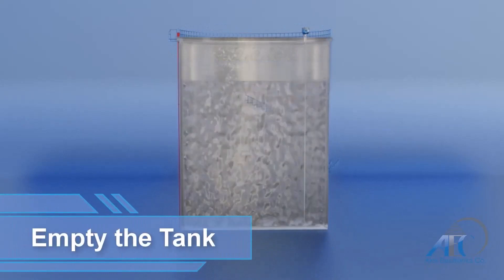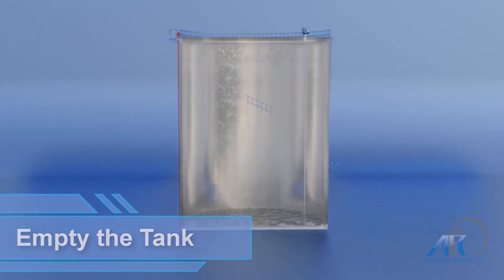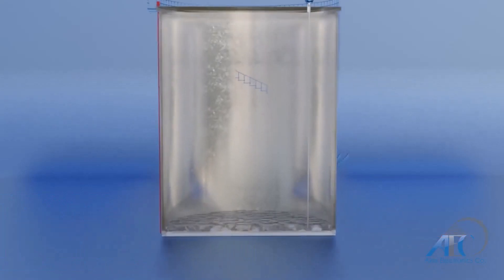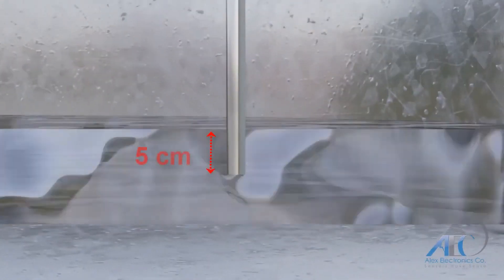After installing, if the tank is full, empty it or set it to the zero level. Note that the measured material should cover about 5 cm of the probe for more accurate results.